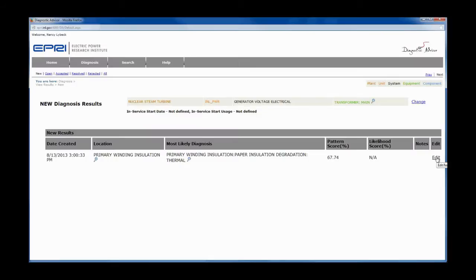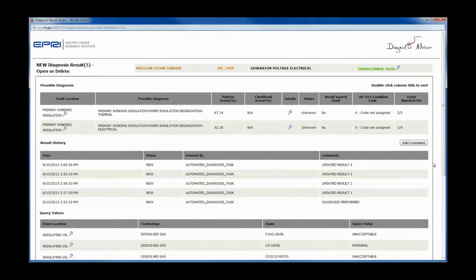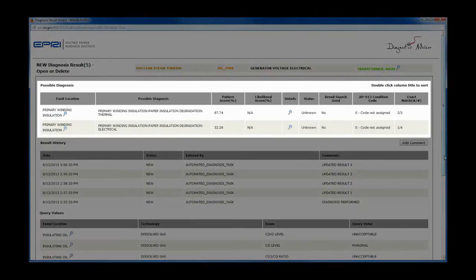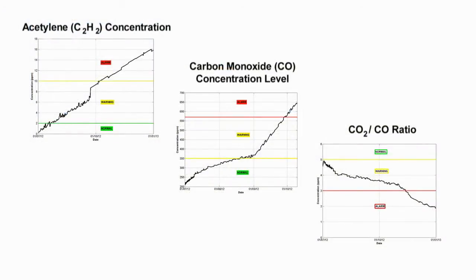As carbon monoxide continues to increase, the ratio of carbon dioxide to carbon monoxide decreases below the recommended level, creating an additional alert. The alert is observed by the Diagnostic Advisor, updating the previous diagnostic results. Due to the evolving symptoms, thermal winding insulation degradation is now identified as the most likely fault. This demonstration highlighted the ability of the Diagnostic Advisor to combine multiple fault features to provide the most complete fault diagnosis possible. As the degradation evolves, the Diagnostic Advisor updates the diagnosis results.